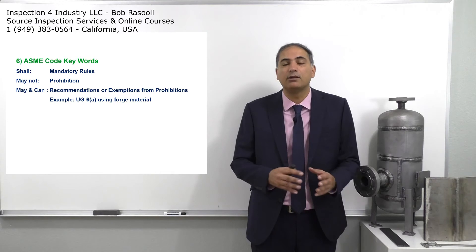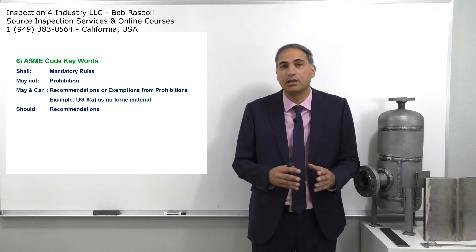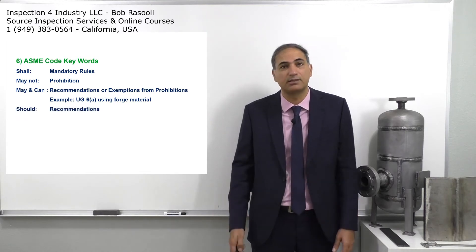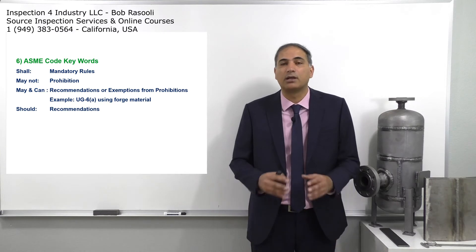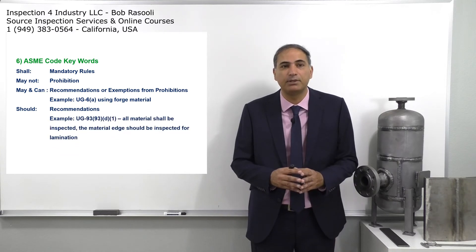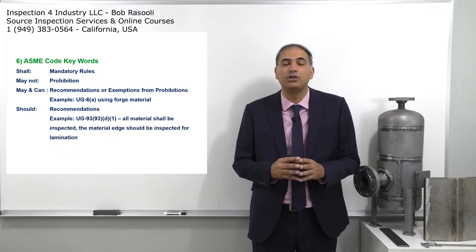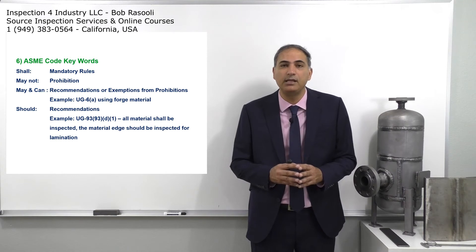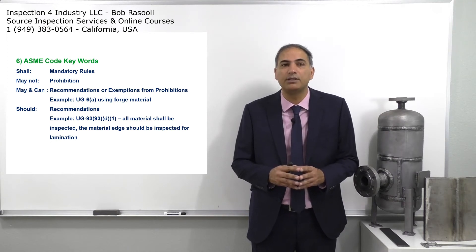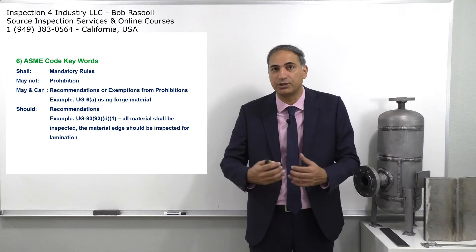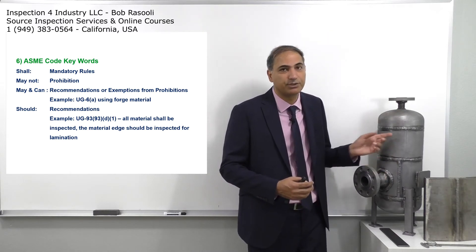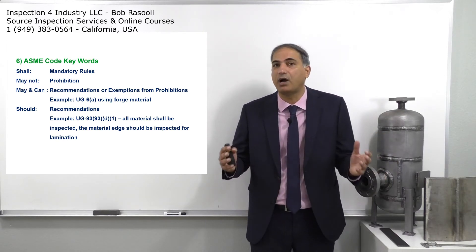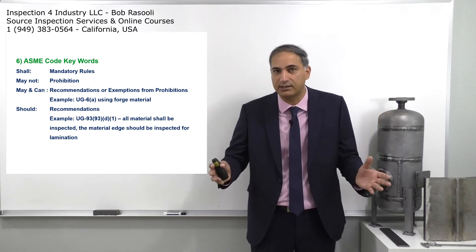Next is 'should,' which is a recommendation — it's not a mandatory requirement. For example, UG-93 D1 says all material 'shall' be inspected. This means all receiving material — for this pressure vessel, we receive this plate material SA-516 Grade 70, which is a common pressure vessel material.